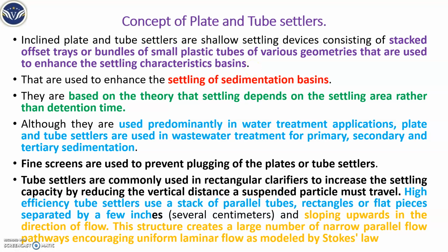These are a stack of offset trays or a bundle of small plastic geometry, and they enhance the settling characteristics of a basin itself. This is based on settling area rather than on detention time. So the more settling area you provide, the more settling will take place, rather than depending on detention time. So they tend to provide more cross-sectional area in this tank.